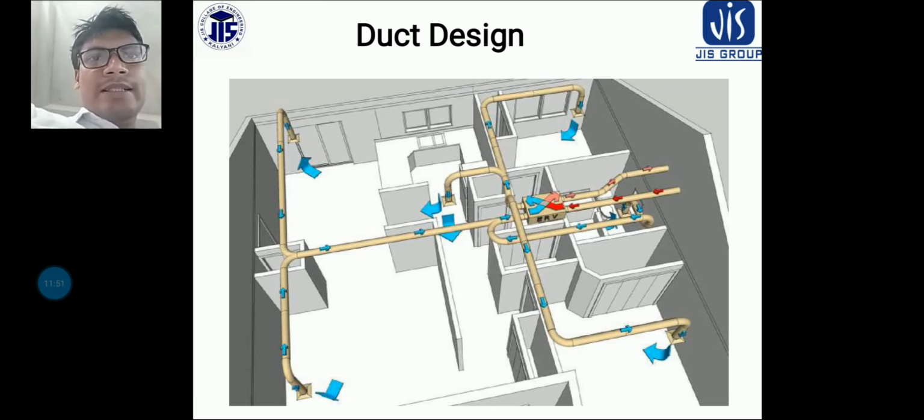The route of the duct should be as direct as possible, to limit the length of the duct and minimize the frictional losses. Next, for changing direction, long radius smooth bends should be used when a sharp right angle turn is inevitable.